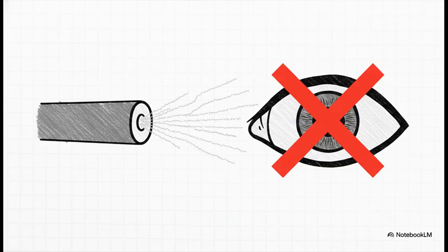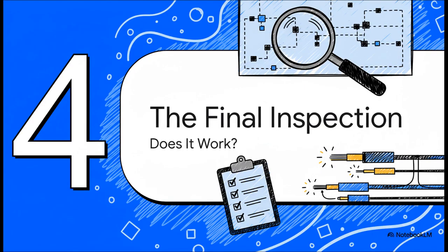And this is the most important warning in the entire document, hands down. The light traveling through these fibers is a laser, but it's often in the infrared spectrum. That means it's completely invisible to the human eye. If you look into a live fiber, you could suffer serious, permanent eye damage, and you would never even see a flash.